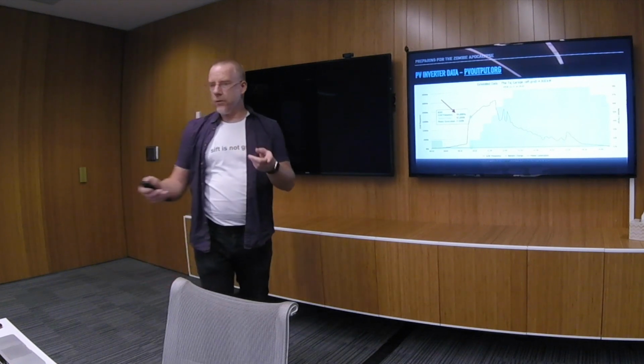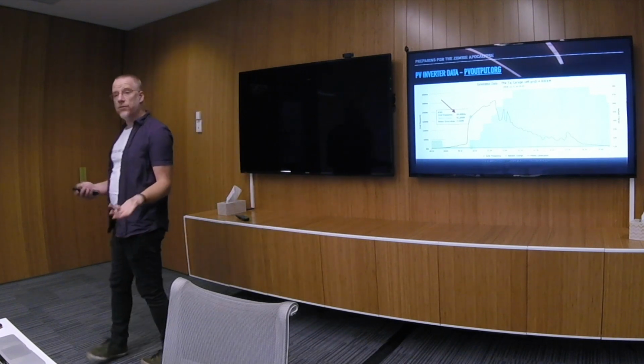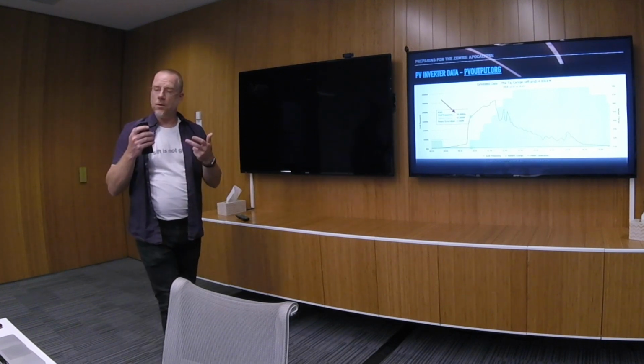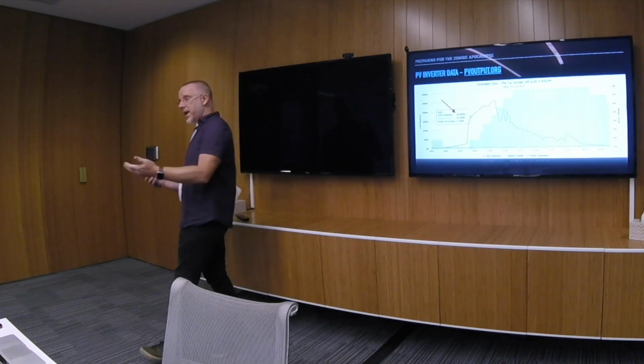So these two inverters, the battery inverter (the yellow one) and the red PV inverter, have to have some way of talking, and there's no data connection between the two. The way they talk is with the grid frequency. The yellow inverter produces the grid, and this is what happens too on the main power grid.